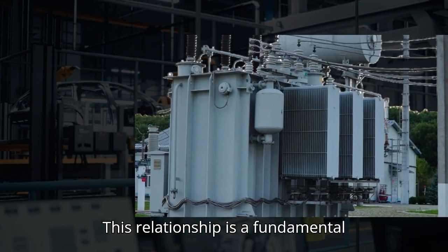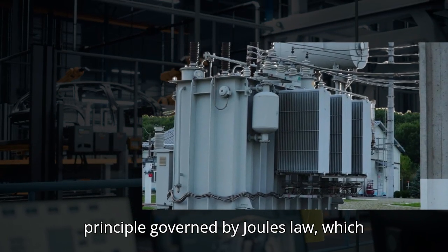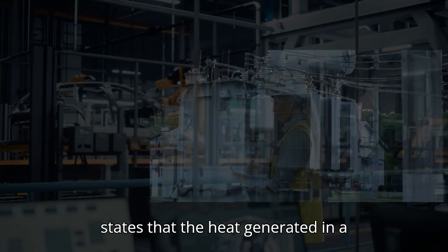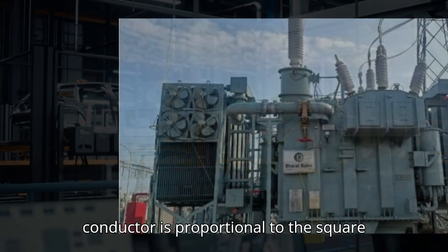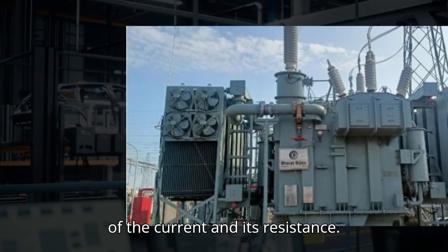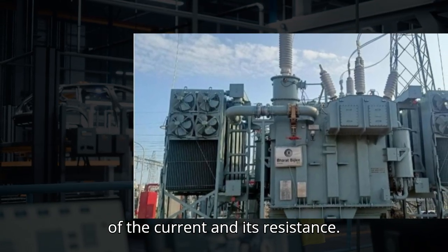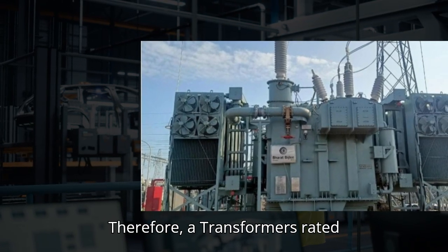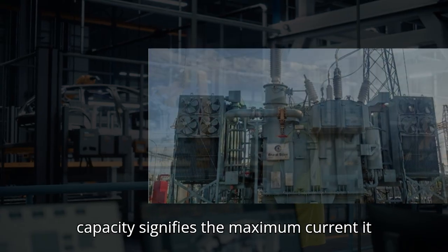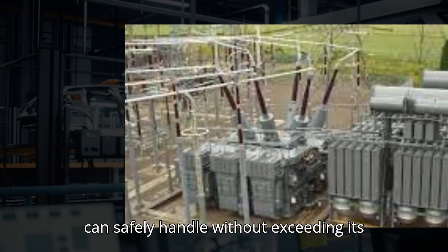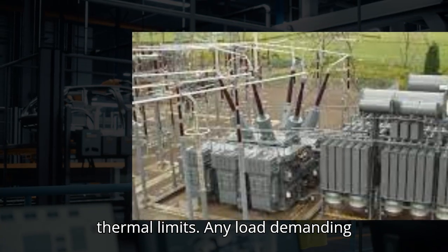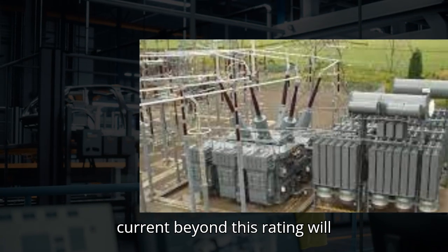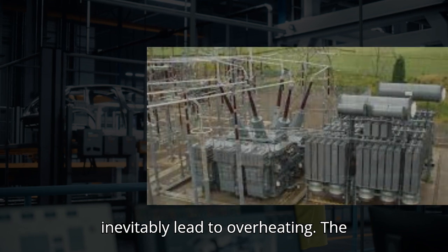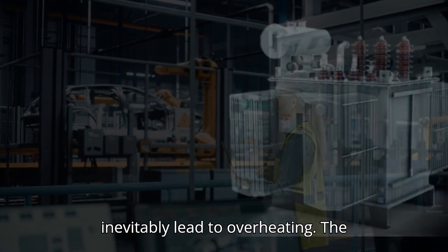This relationship is a fundamental principle governed by Joule's law, which states that the heat generated in a conductor is proportional to the square of the current and its resistance. Therefore, a transformer's rated capacity signifies the maximum current it can safely handle without exceeding its thermal limits. Any load demanding current beyond this rating will inevitably lead to overheating.